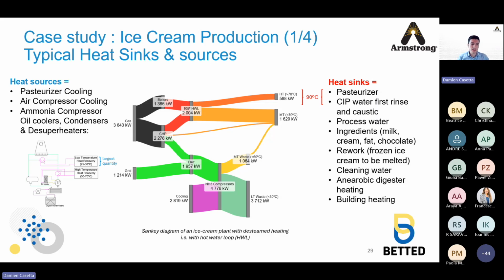And what we can see is that the main source here is cooling, and that's what we have in purple here. The cooling basically is coming through pasteurization cooling, air compressor cooling, but also mainly chillers. And in chillers, you get heat from the compressor oil coolers, the condensers, and the desuperheaters, which are shown at the left of the slide. So you basically have two temperature levels. You have low quantity, high temperature heat on the desuperheaters and the oil coolers between 50 to 70 degrees, and low temperature but high quantity of heat on the condensers between 25 and 30 degrees.